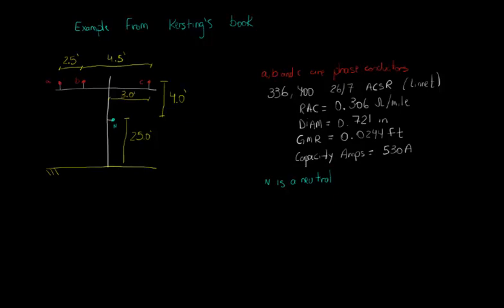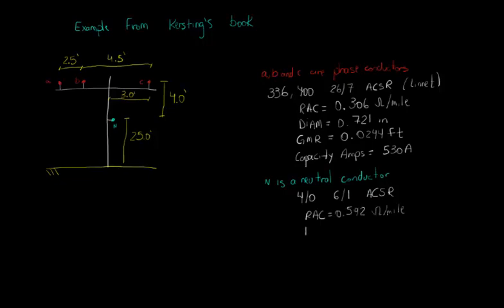The neutral conductor is defined with a size of 4/0, a stranding of 6 over 1 and the material is ACSR as well. The AC resistance is 0.592 ohms per mile. The diameter is equal to 0.563 inches and the GMR is equal to 0.00814 feet and the capacity is 340 amps.